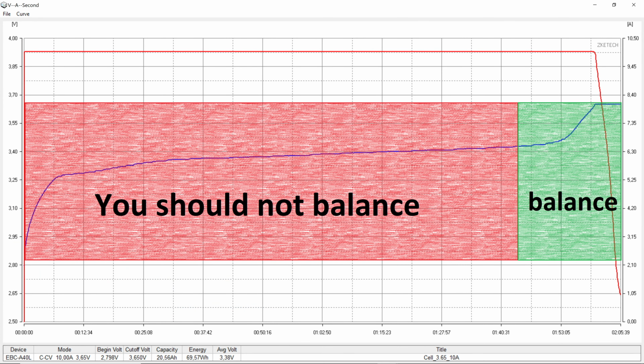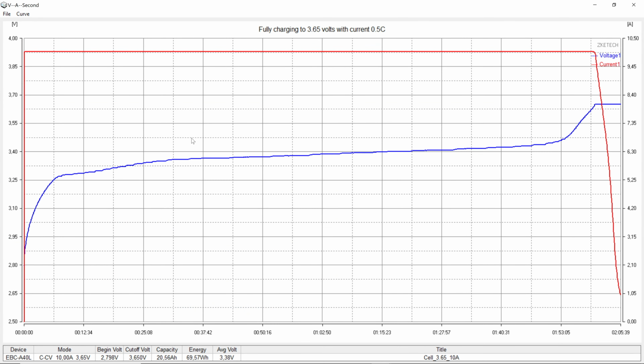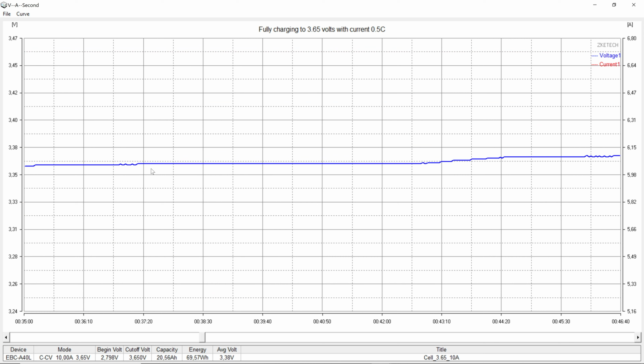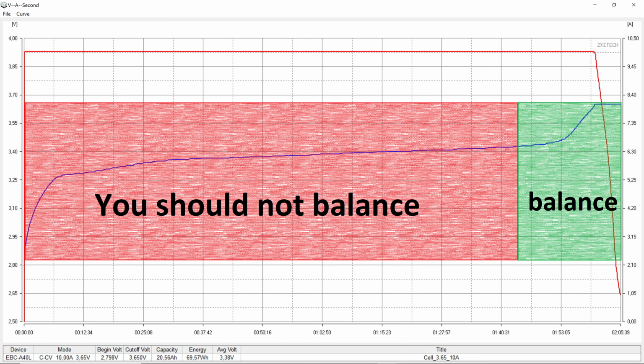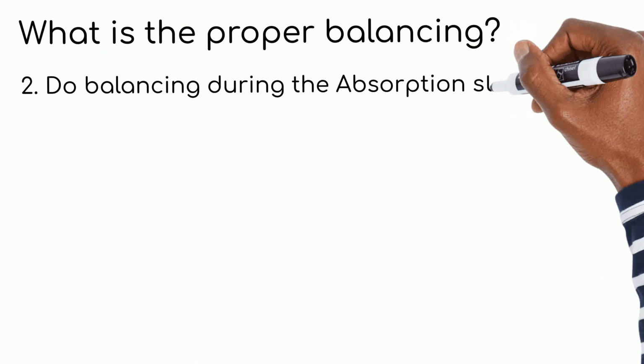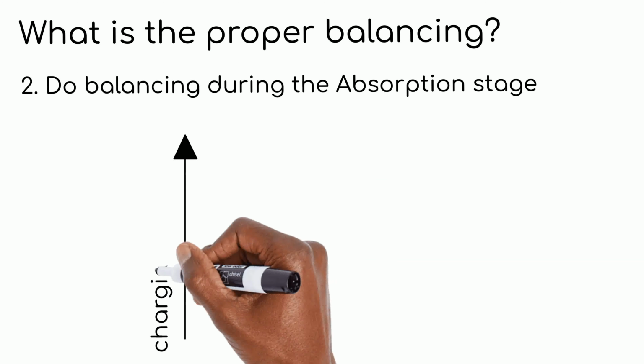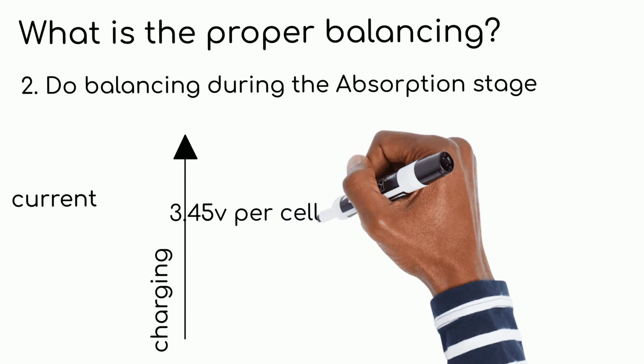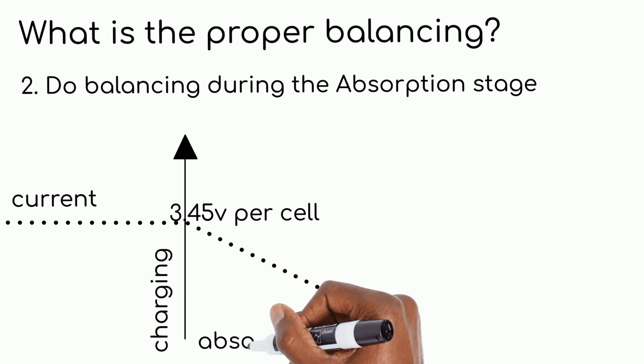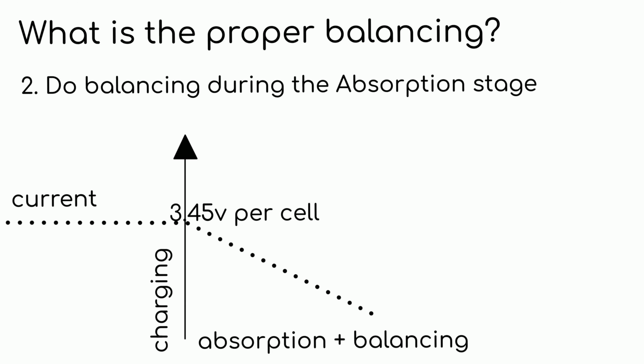Second, balancing should not be carried out on flat sections of the LFP charging curve, at which point the cell capacity increases, but the voltage does not change. This often leads, on the contrary, to cell imbalance. It is better to start balancing no earlier than 3.4 volts per cell. If you are charging the battery to 3.45 volts per cell, it is probably a good idea to start balancing at absorption at that same voltage of 3.45 volts per cell and 13.8 volts per battery.